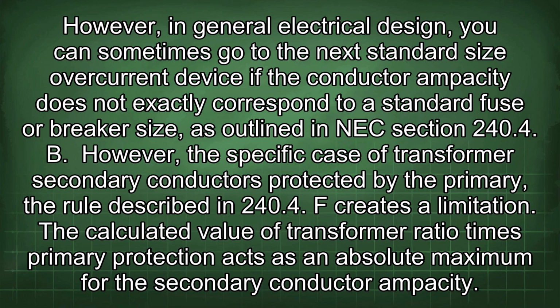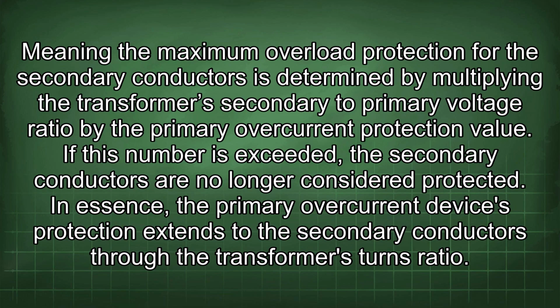However, for the specific case of transformer secondary conductors protected by the primary, the rule described in 240.4(F) creates a limitation. The calculated value of transformer ratio times primary protection acts as an absolute maximum for the secondary conductor ampacity, meaning the maximum overload protection for the secondary conductors is determined by multiplying the transformer's secondary to primary voltage ratio by the primary overcurrent protection value. If this number is exceeded, the secondary conductors are no longer considered protected.